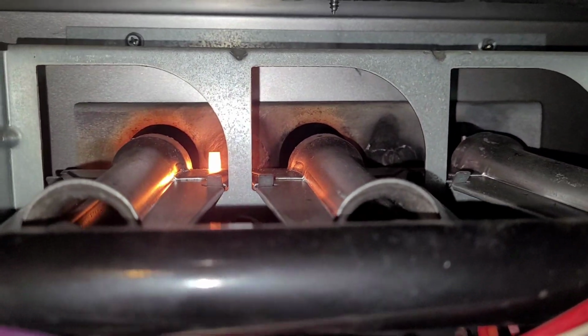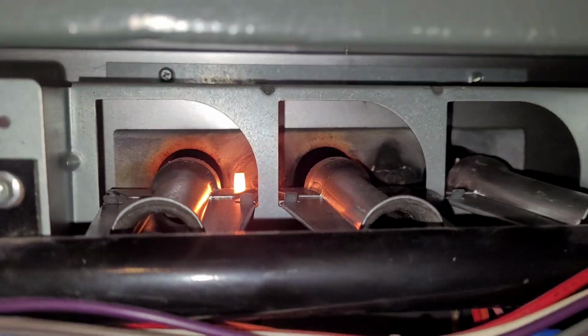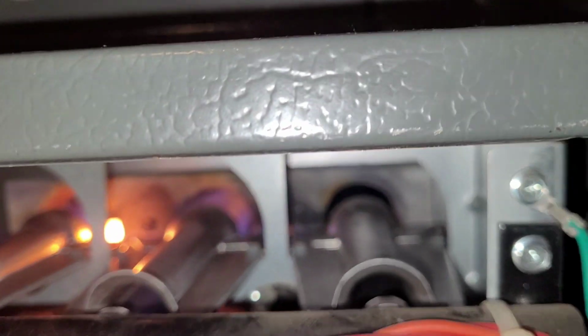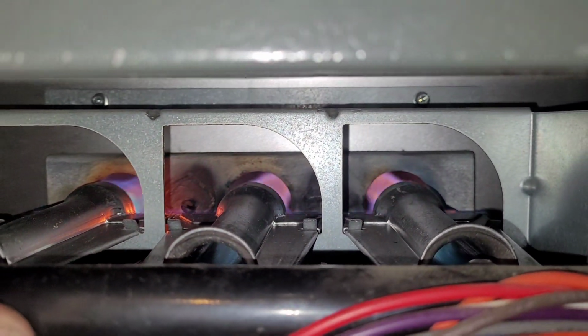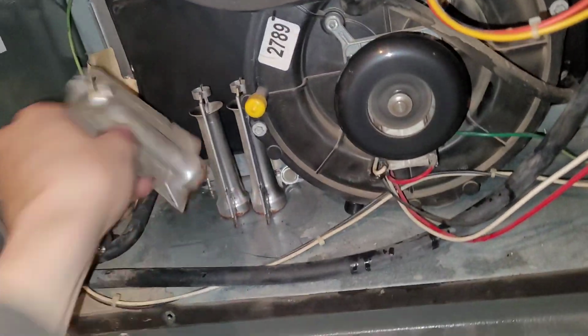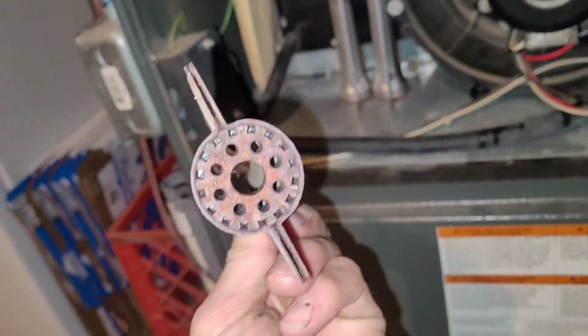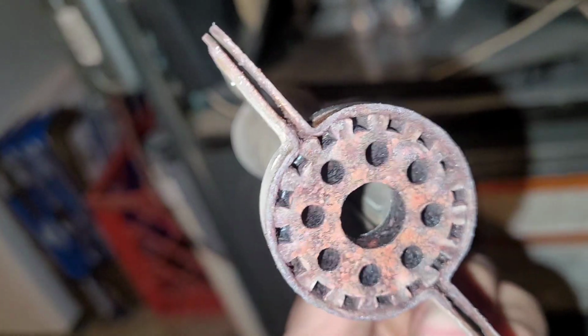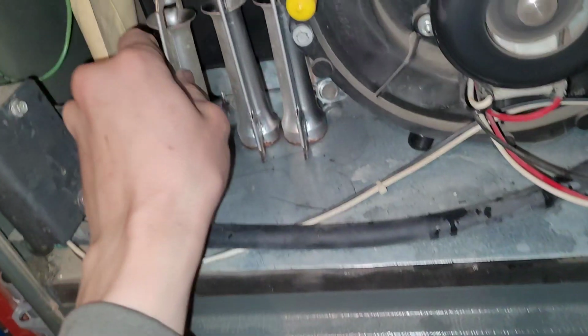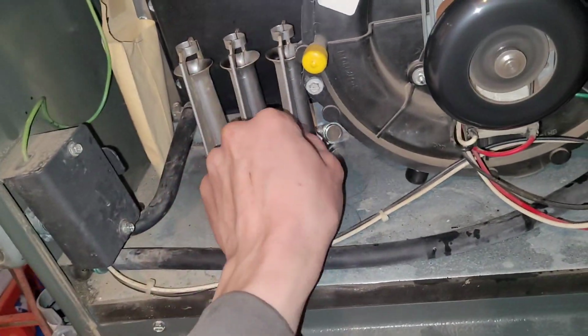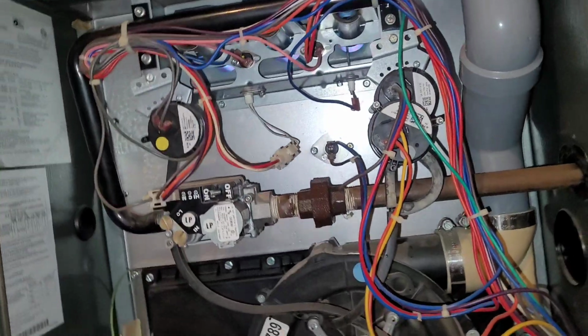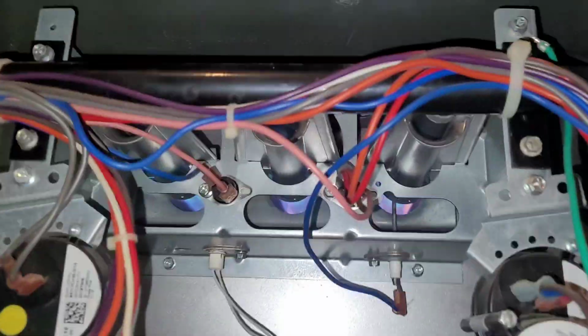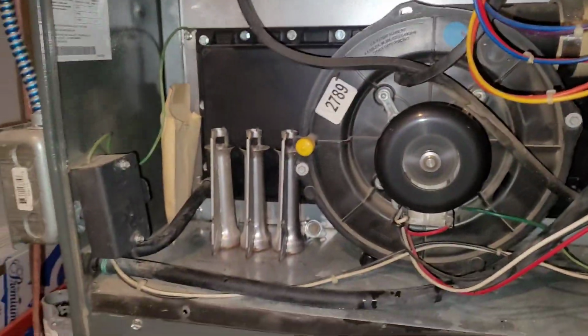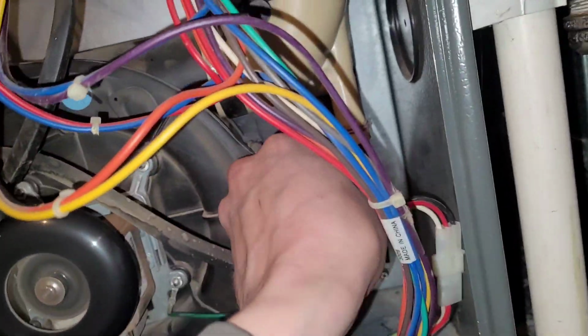Let's see if she lights. Beautiful. The old burners weren't actually that bad, but in the corners you can see they were kind of starting to crust over, so I just recommended a new set of burners, because if they're not quite burning right, it can take out the new heat exchanger pretty quickly. So go out and check the combustion, but we should be pretty much good to go.